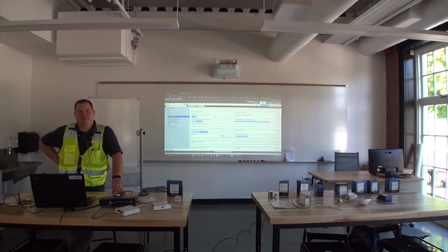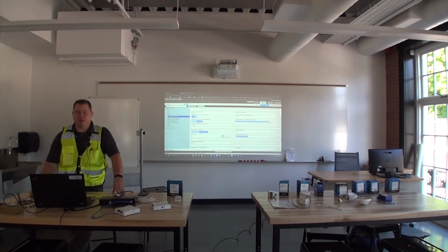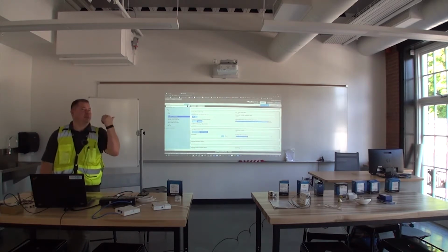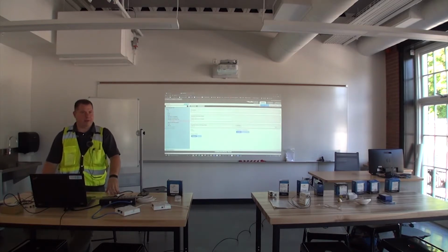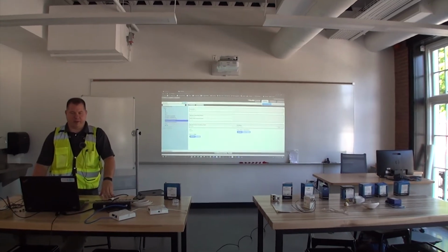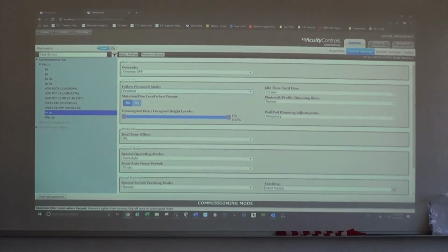So the easiest way to adjust it is what you're doing there, but how about completely disabling it for the library? Like I was saying earlier, you can unplug the sensor, or if you can't reach it because it's in the library, you go to the power pack and tell it to stop following the photocell — it's the photocell follow mode, you just disable it, and tell the power pack, stop following the photocell, you dumbass.